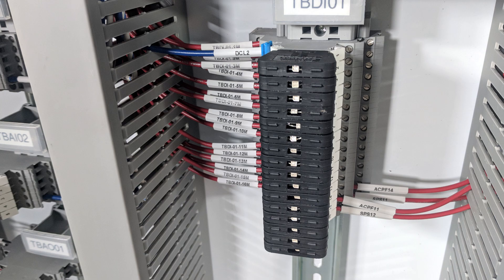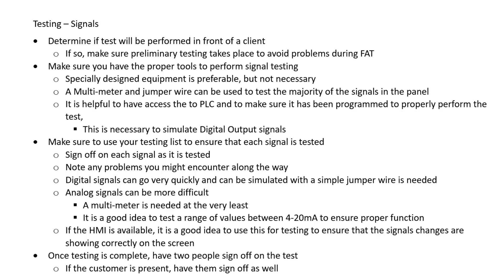With digital signals, you can in many cases simply use a jumper wire connected to power and then touch it to each signal so that you can simulate the on-off state that a digital signal requires. Just using a jumper wire in a lot of cases is acceptable if you don't have any kind of special equipment.